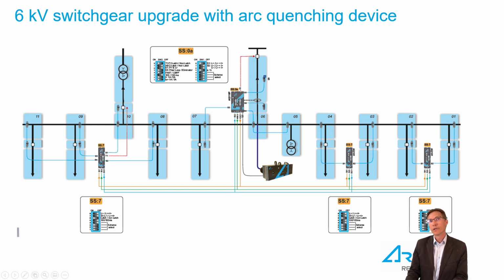Then we have in the outgoing feeder bays, I/O extension units, you could call them, for accommodating enough arc sensors into the system. And the actual arc quenching device is bolted, as I already mentioned, in the VT section. And this always comes into the consideration of where you find the space, where it is most convenient to locate. And in this particular application, the VT section provided enough space for installing the arc quenching device.